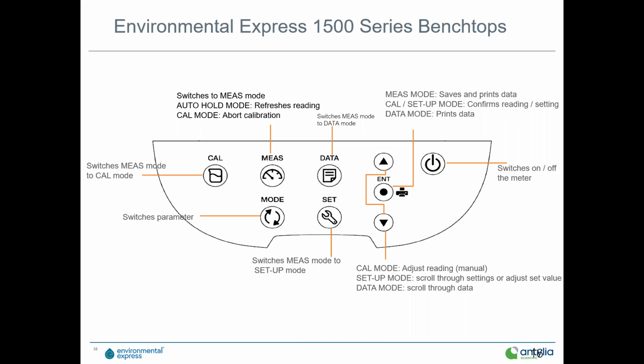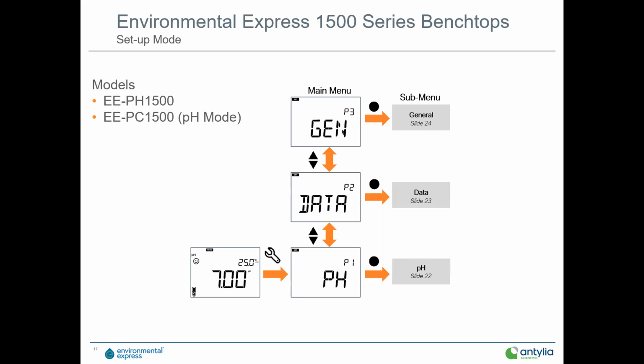So I did want to give a quick overview of the programs and sub-programs in the 1500 instrument. The beauty of this is if you can understand and get the flow of the programs and sub-programs for the 1500, using the 2000 is exactly the same. The only difference would be there's some additional sub-programs to it. So quickly to go through some of the key basic programs, and there's 3 basic programs. You've got your measurement mode, lower left here. You would push the settings button that would put you into pH, up and down arrow to go to data, and then up and down arrow again to go to general.